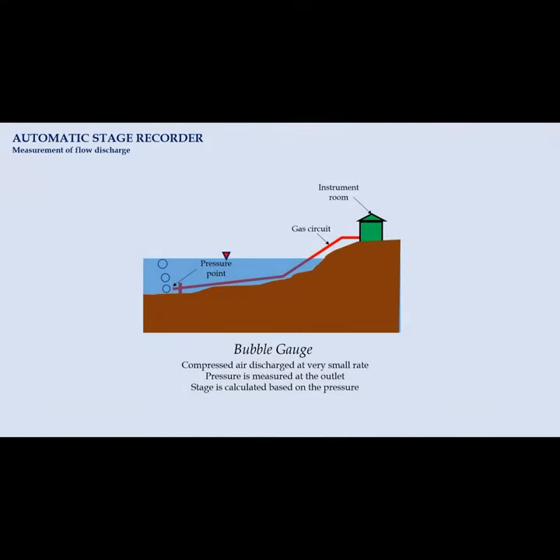Other than a float gauge recorder, a bubble gauge may be used. Compressed air is discharged through the outlet of a gas circuit located at the bottom of the river at a very small rate. As soon as the gas discharges, the gas pressure will be measured. This pressure equals the depth of water above the outlet.